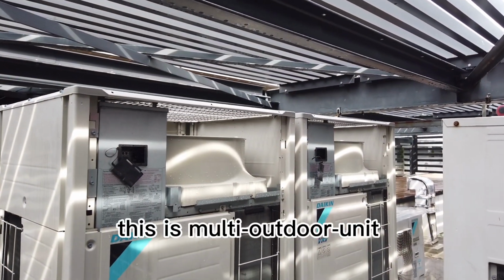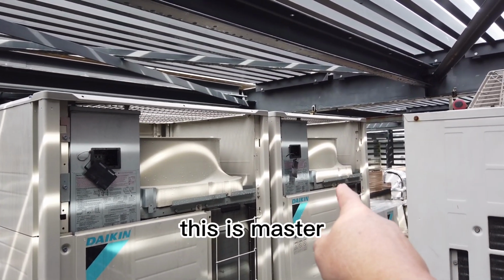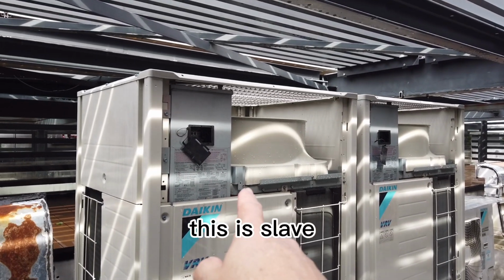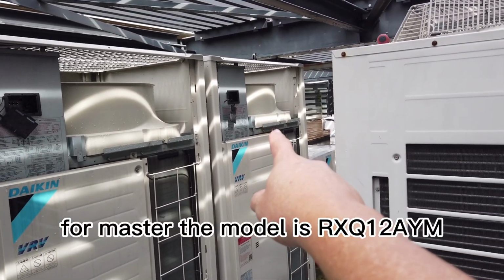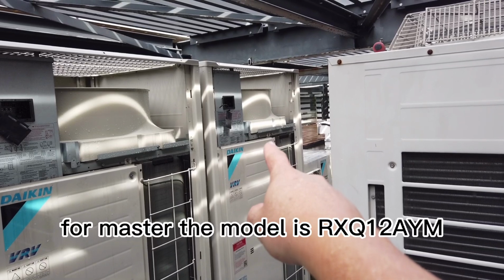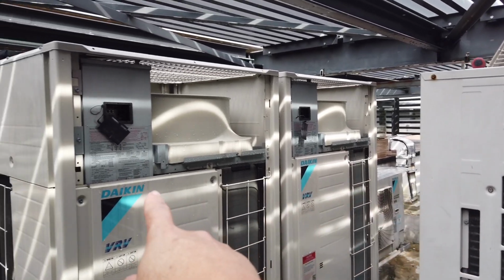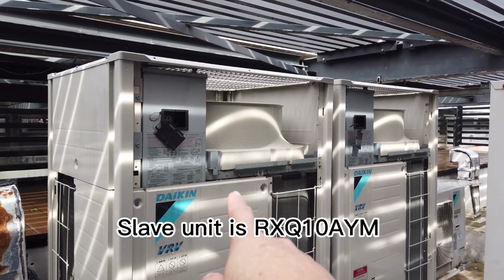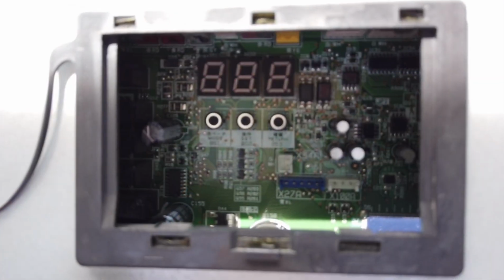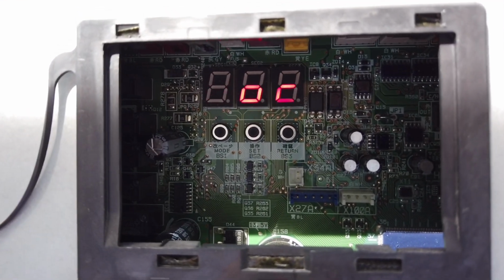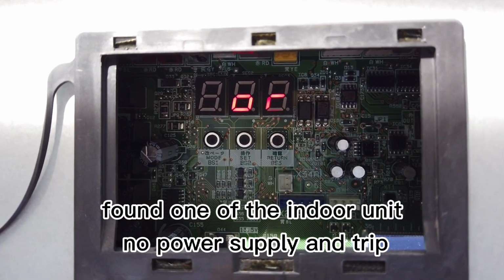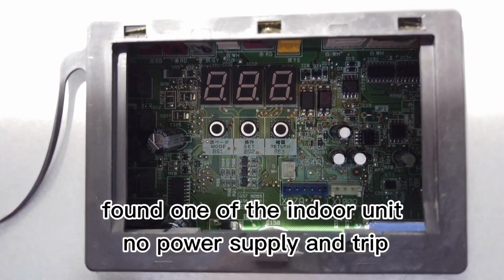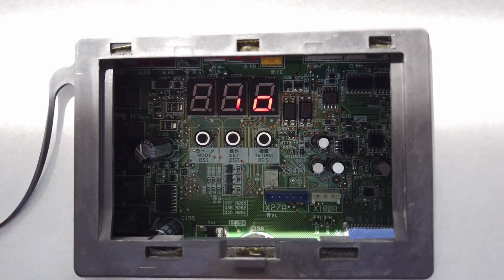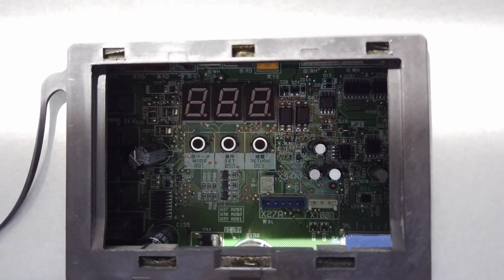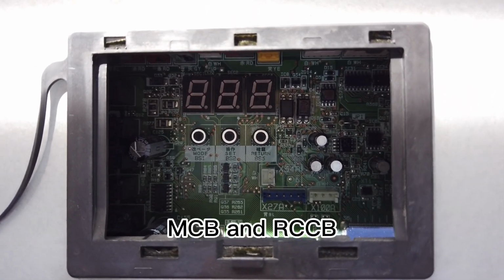This is a multi outdoor unit. This is master, this is slave. For master, the model is RXQ12AYM. Slave unit is RXQ10AYM. Now we found one of the indoor units has no power supply and trip. Actually, it's trip MCB and RCCB.